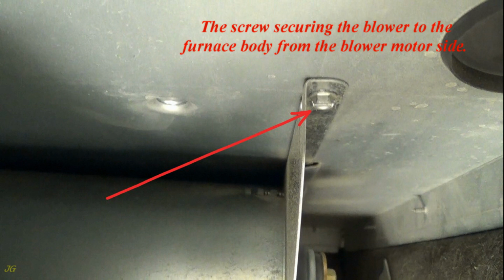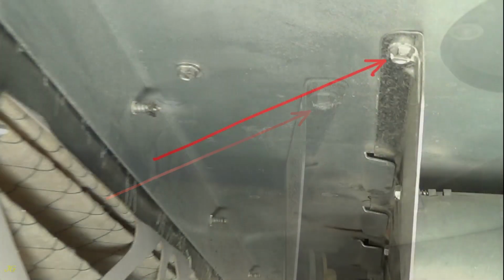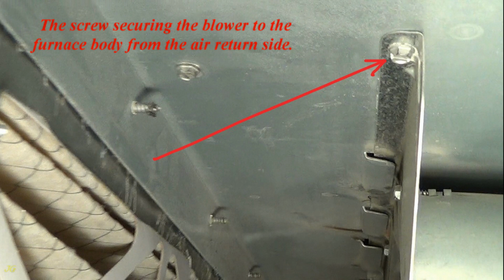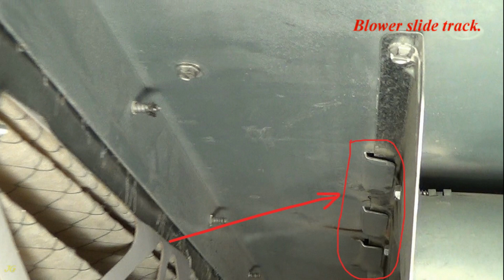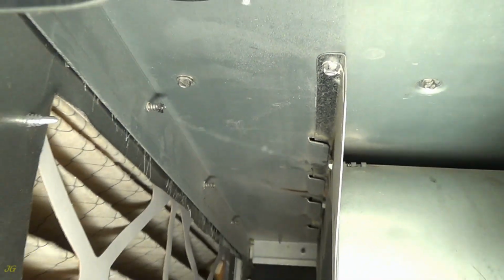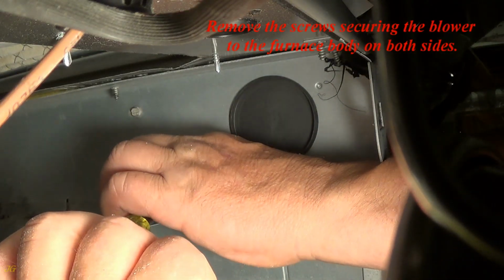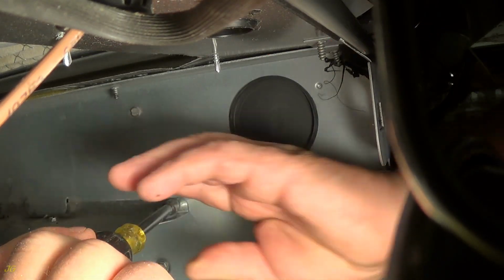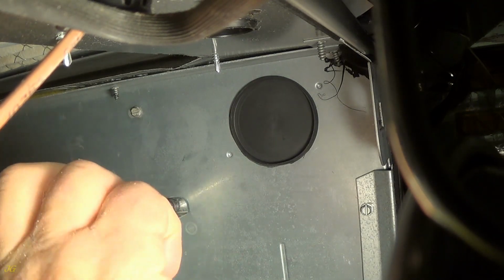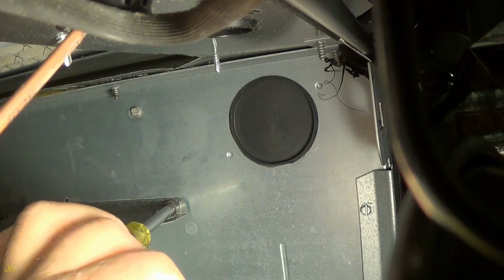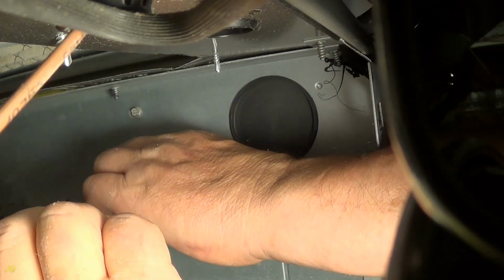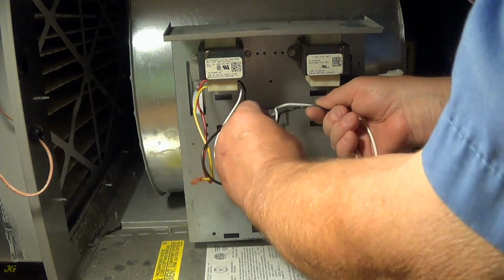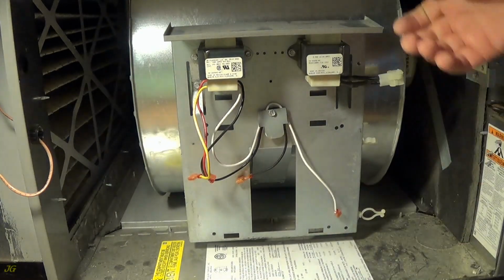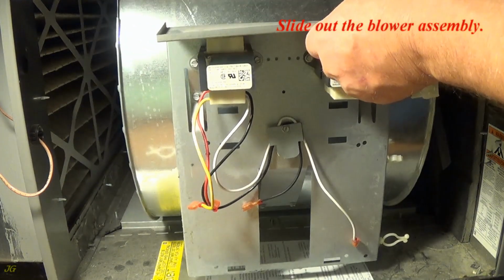The screw securing the blower to the furnace body from the blower motor side. The screw securing the blower to the furnace body from the air return side. Blower slide track. Remove the screws securing the blower to the furnace body on both sides. Slide out the blower assembly.